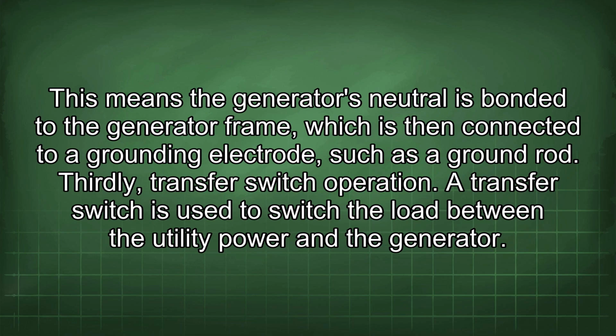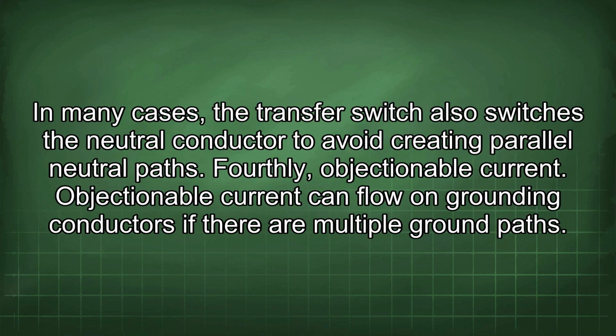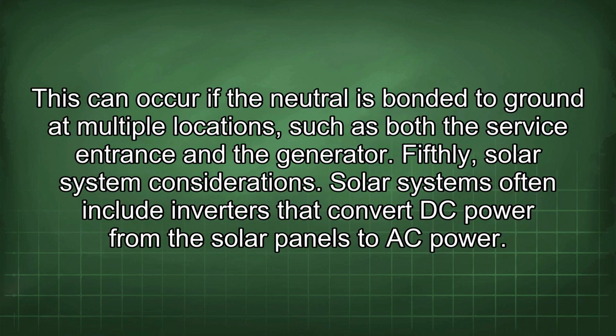Thirdly, transfer switch operation. A transfer switch is used to switch the load between the utility power and the generator. In many cases, the transfer switch also switches the neutral conductor to avoid creating parallel neutral paths. Fourthly, objectionable current. Objectionable current can flow on grounding conductors if there are multiple ground paths. This can occur if the neutral is bonded to ground at multiple locations, such as both the service entrance and the generator. Fifthly, solar system considerations.